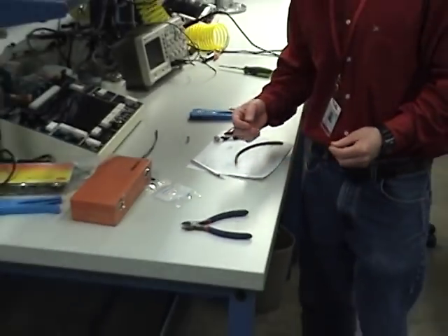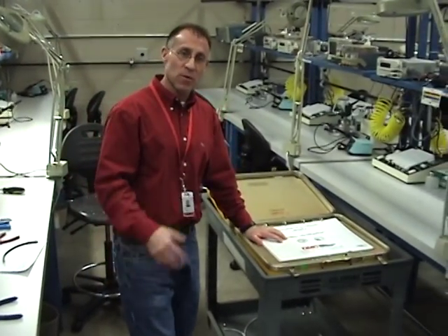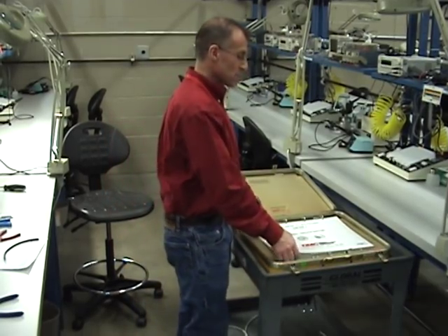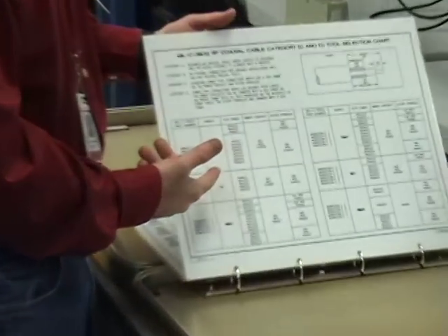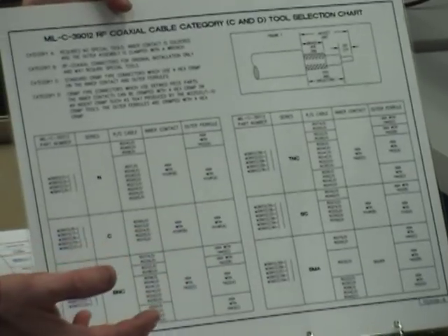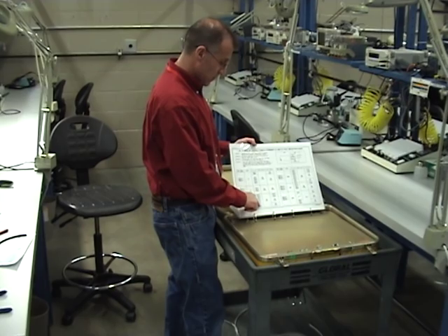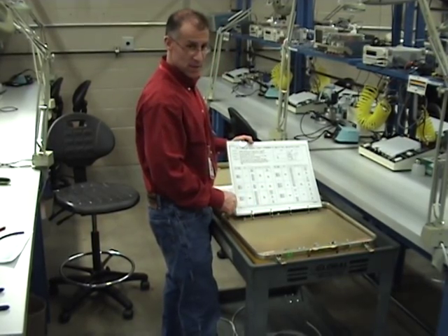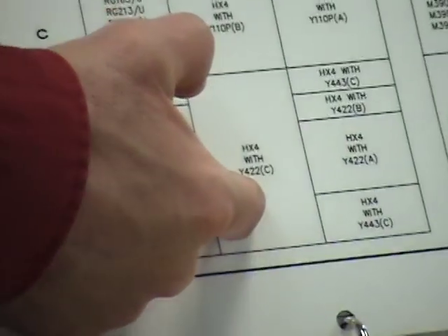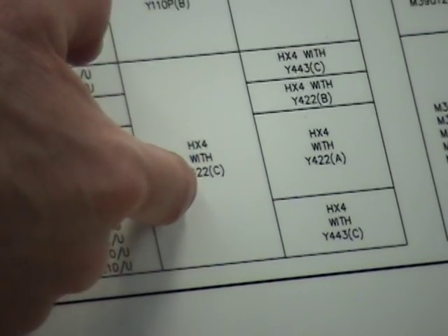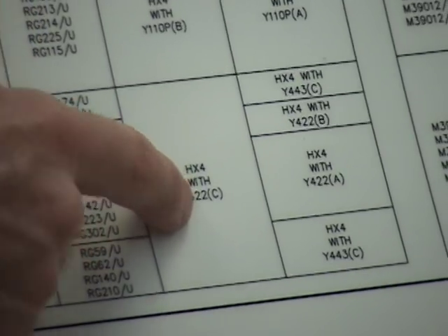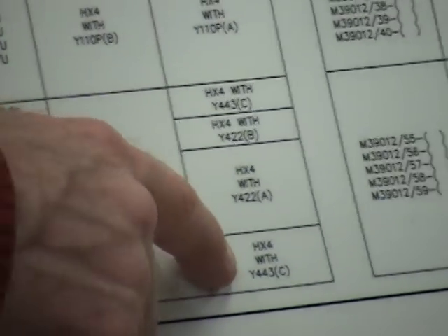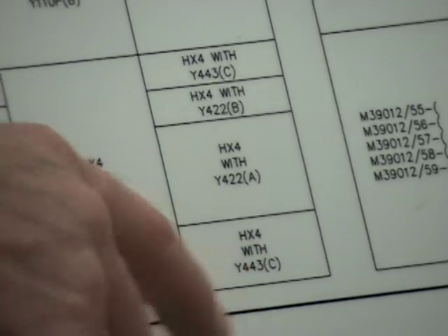So what tools do I need to make that crimp? I'm simply going to come over and look at my DMC kit. The same kit we used earlier on MS connectors. I look through my chart and on the very back side, it talks about coax cable. The type of wire and the type of connector matters. I'm going to look. RG-59. That's what I'm about to use. And it's a BNC connector. RG-59 BNC. And it tells me my inner contact, what tool handle I'm going to use. I'm going to use an HX4 with a Y422 die. And I'm going to use the C slot. And then the outer ferrule, same handle HX4, but I'm going to use it with a 443 die C slot.